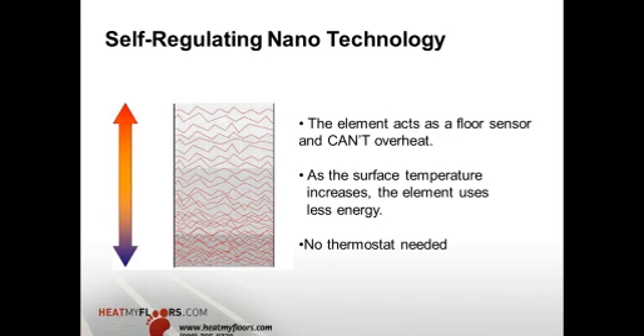The STEP warm floor technology with self-regulation can't get over the desired temperature. As the surface temperature increases and gets closer to achieving 82 degrees with our 7.8 watt product, it needs less energy to maintain that temperature. Once it achieves that, it maintains it very well across the floor, and no thermostat is needed.